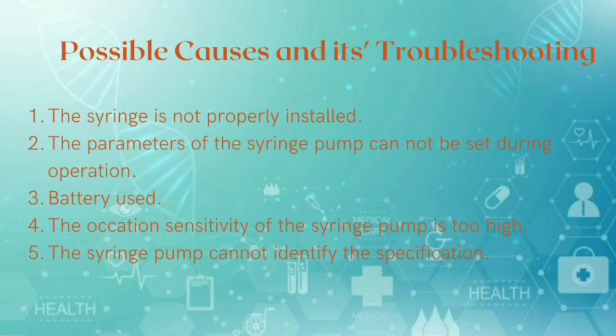Next one is the parameter of the syringe pump can't be set during the operation. In this situation, the injection rate does not change. To fix that issue, press stop key and then press select key to set the parameters.